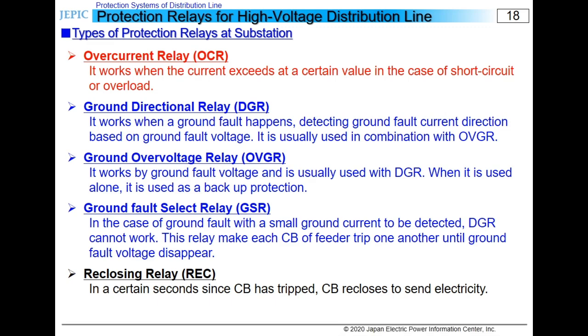Blue ones are for ground fault. Ground direction relay is also installed to every feeder, and when a ground fault occurs, it detects its ground fault current comparing with ground fault voltage and judge whether the ground fault occurs in each feeder or not. Ground over voltage relay detects ground fault over voltage. Ground directional relay and ground over voltage relay are combined to identify in which feeder a ground fault occurs, and then makes CB trip, and its work time of CB trip is 0.8 seconds.